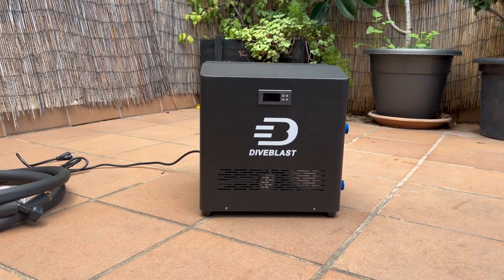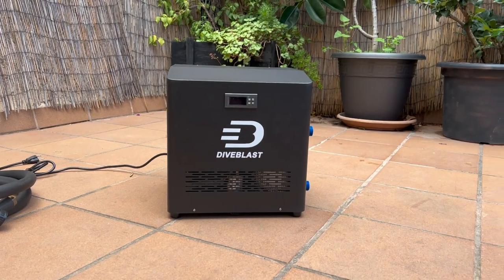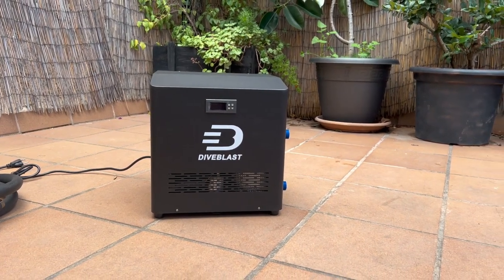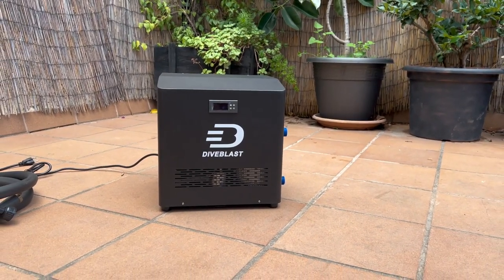Step 2. Before powering the chiller, make sure it's upright and stable. Let it sit for 24 hours after transport to allow the refrigeration fluid to settle. Skipping this step could lead to chiller malfunction.